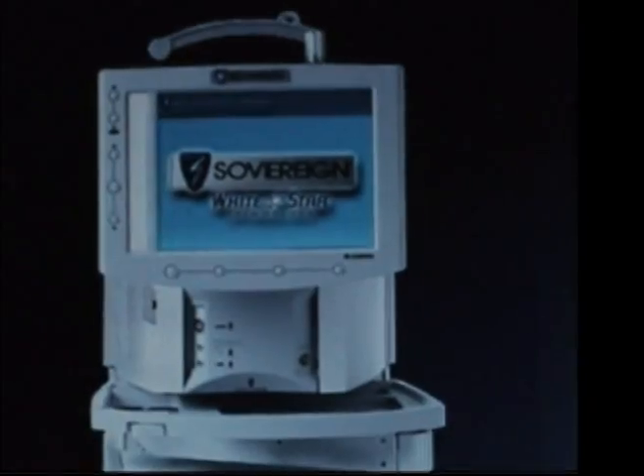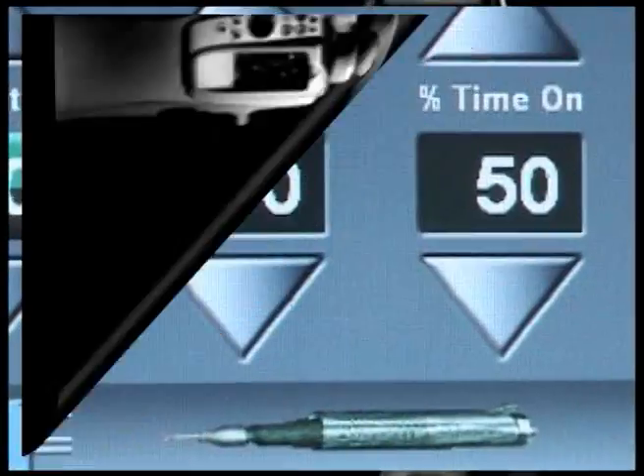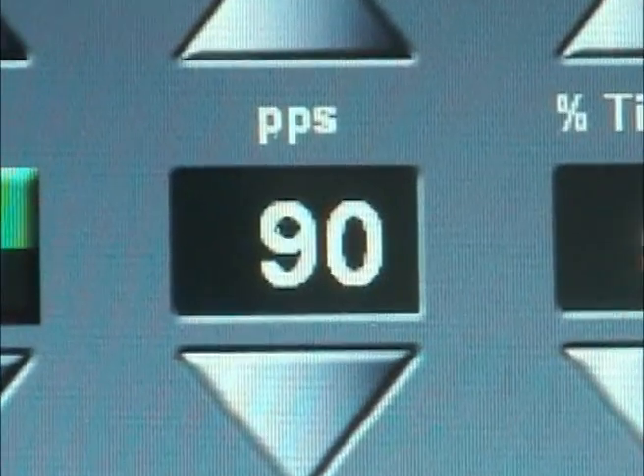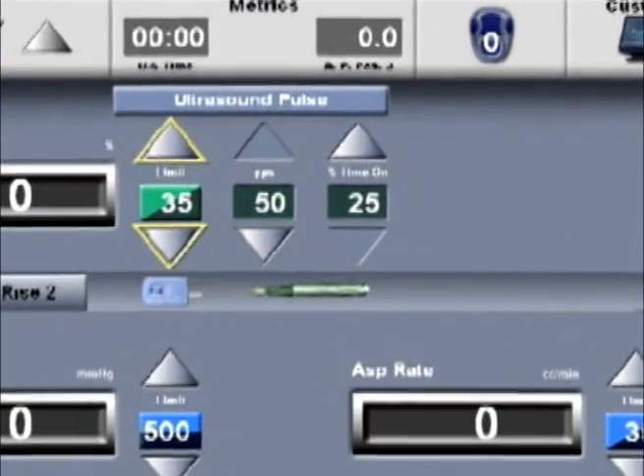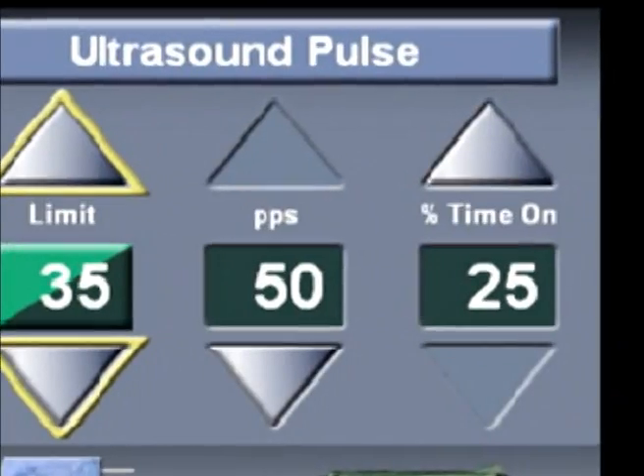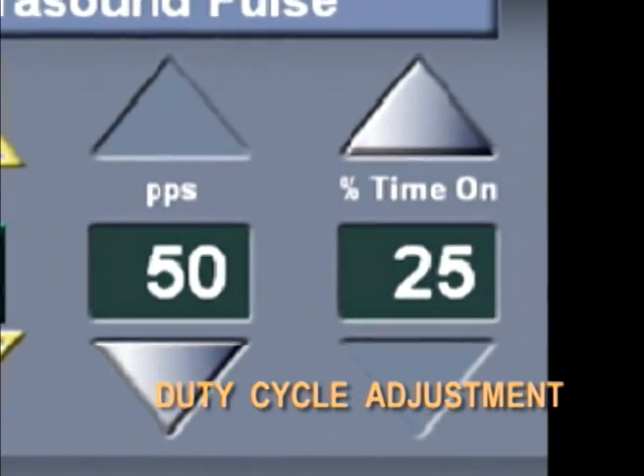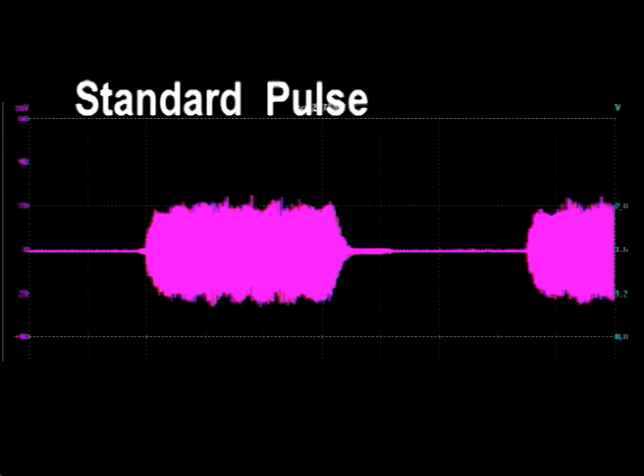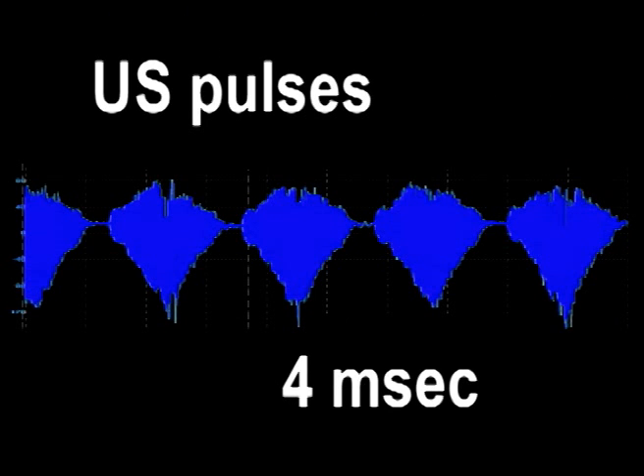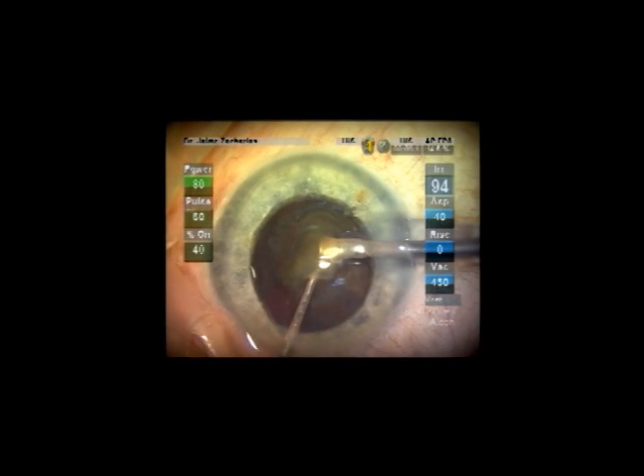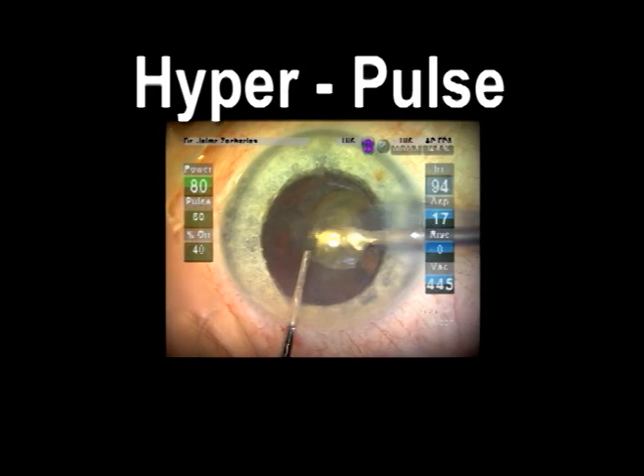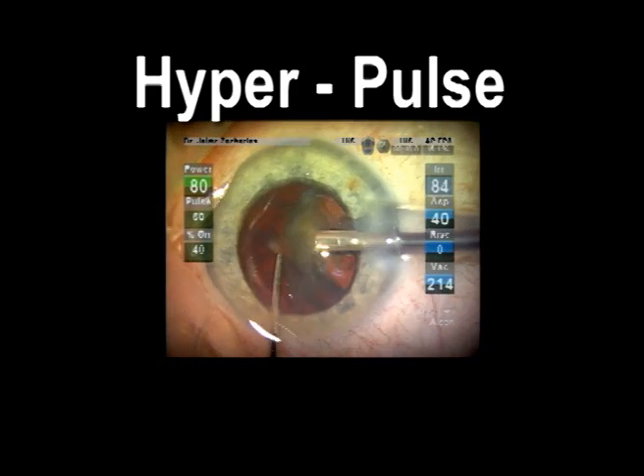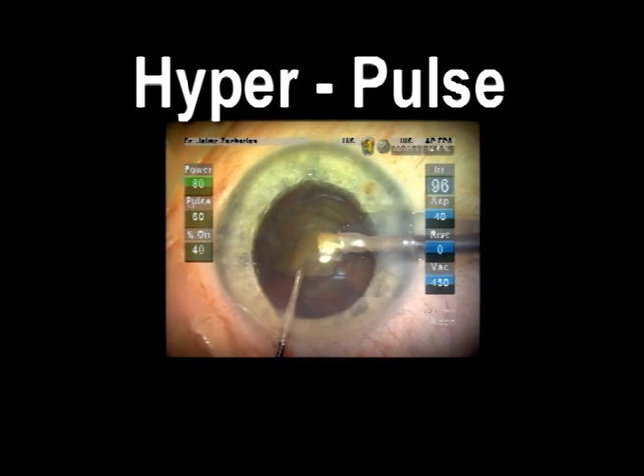Newer FACO consoles have expanded the adjustment possibilities of pulse mode, providing repetition rates above 15 and up to 90 pulses per second. These systems also allow setting the duty cycle departing from the typical 50% on, 50% off ratio. Pulse duration can be shortened down to 4 ms with this modality. This extended range pulse mode has been termed hyperpulse mode, and relevant surgical advantages have been associated with it.